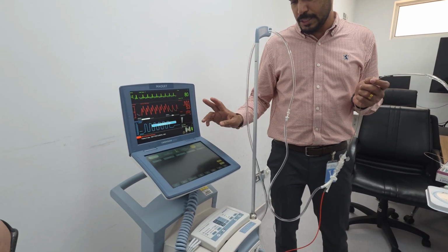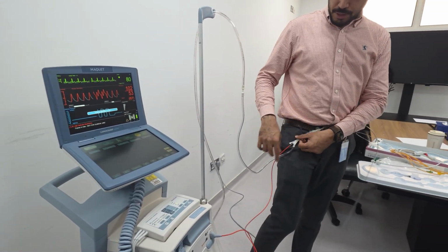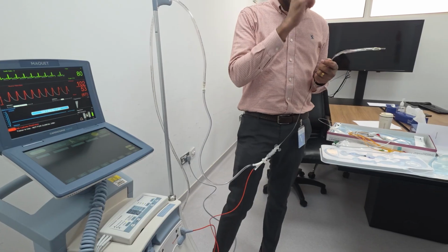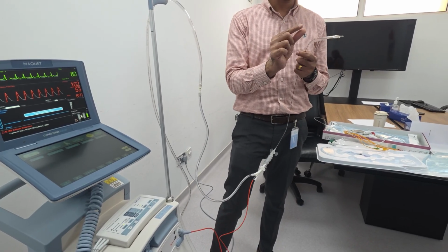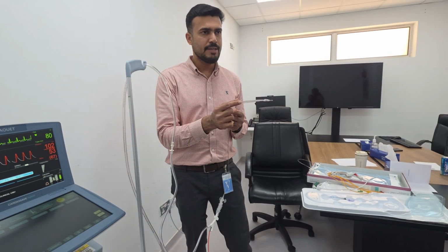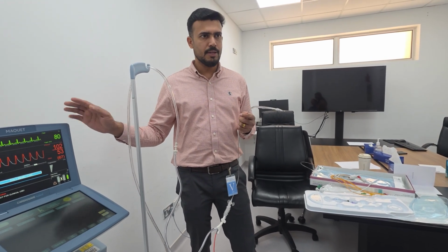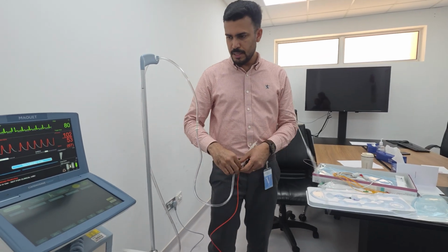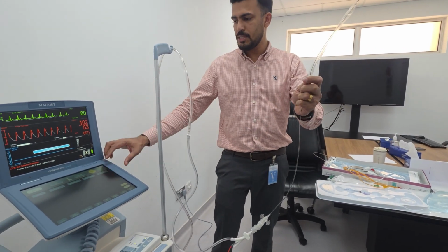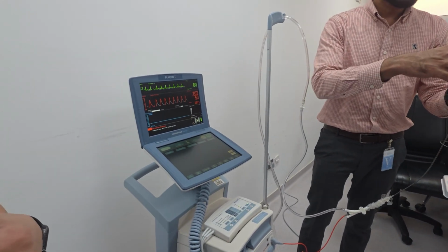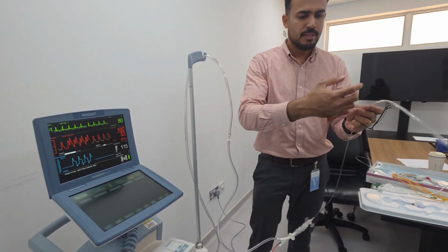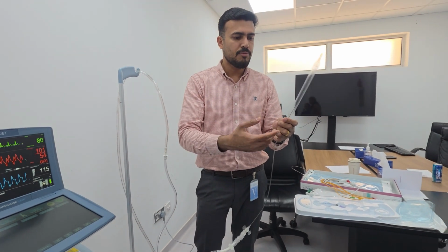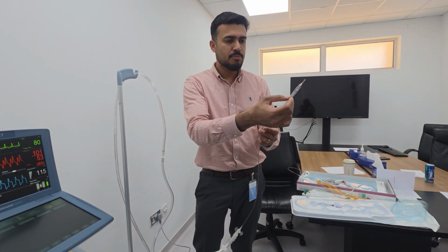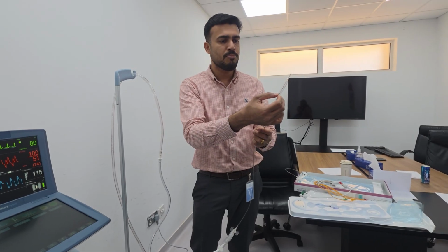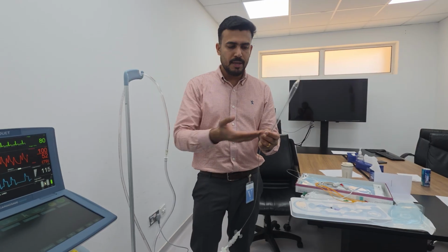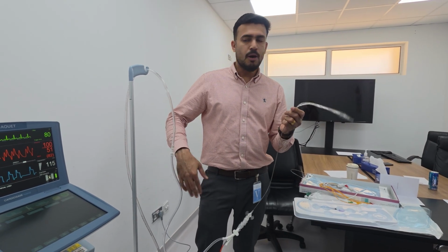So you can mute it for 1 minute. You find any blood, maybe a leakage happened. If there is any small gas difference, more than 5 cc, it will be considered a leakage alarm and give you a gas loss alarm. Just have a look here. I'm ignoring the alarm and simply starting again. I told you the helium lasts 2 hours. Maybe after 1 hour, when it's doing an autofill, there is a small pinhole perforation here with a small amount of blood. It will keep swelling here, but during the autofill it will suck the blood inside the machine. So how to avoid this?